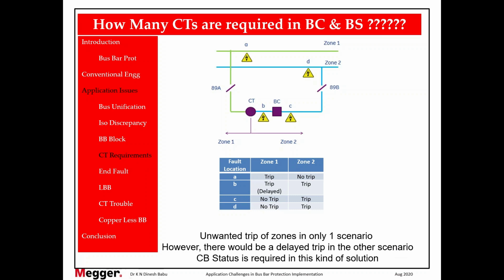And one more important point: circuit breaker status is required for this kind of solution. What happens if the status fails? Worst case scenario, breaker feedback is not coming to the relay. For that, we also created a sophisticated algorithm in such a way that whenever zone 2 trips, we add a timer. The zone 2 trip output is added to a timer. The timer should be greater than your breaker operation time. After the timer, this CT will be removed from the picture. So even if your breaker feedback has failed and is not coming to the relay, the secured algorithm will still work as a backup.